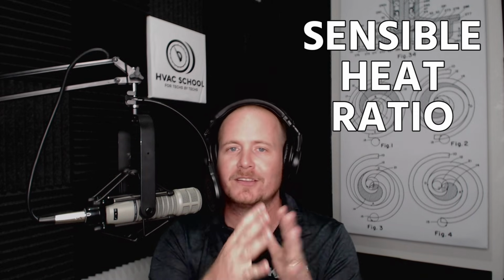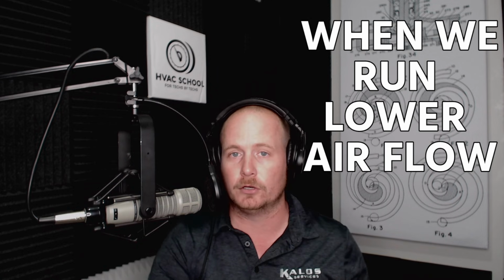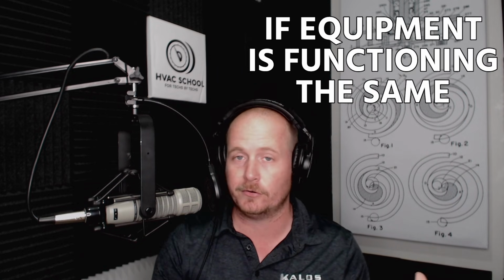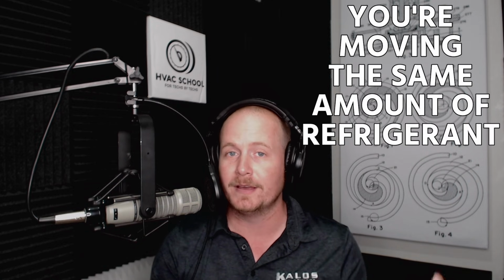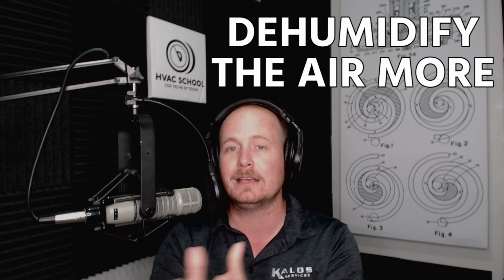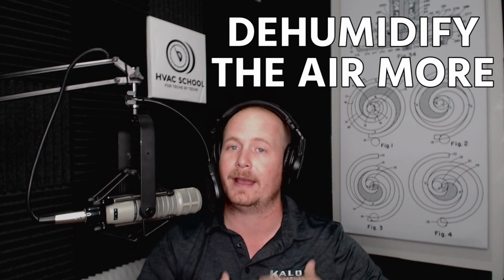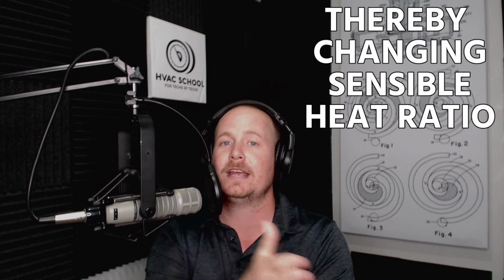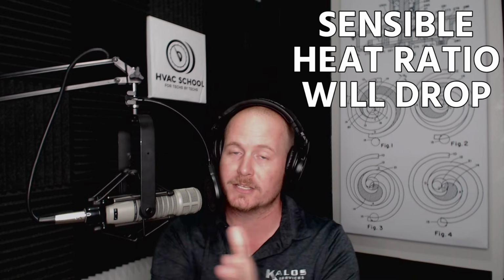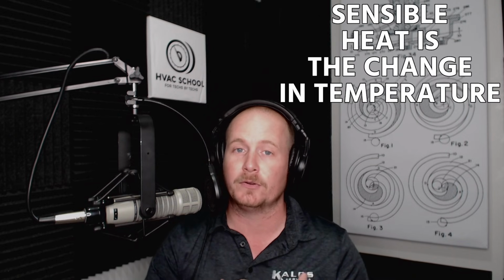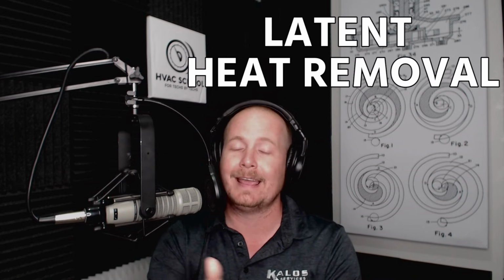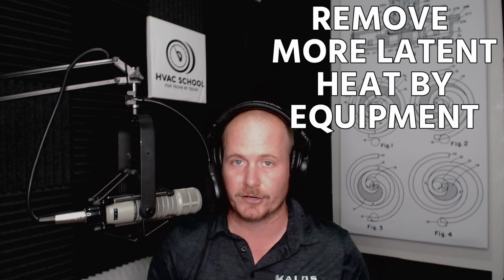It's something that we call sensible heat ratio, or SHR. When we run lower airflow over an evaporator coil, if the piece of equipment is functioning the same, meaning you're moving the same amount of refrigerant, then you're going to dehumidify the air more because you're going to have a colder coil, thereby changing your sensible heat ratio, meaning your sensible heat ratio is going to drop. Sensible heat is the change in temperature, and latent heat removal is the moisture extracted from the air.